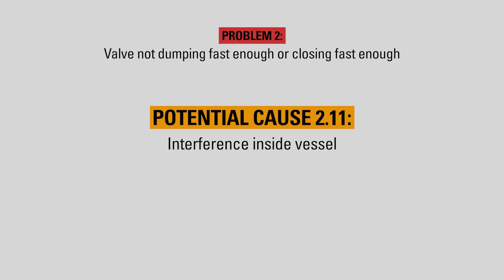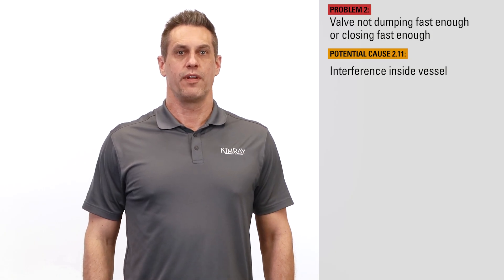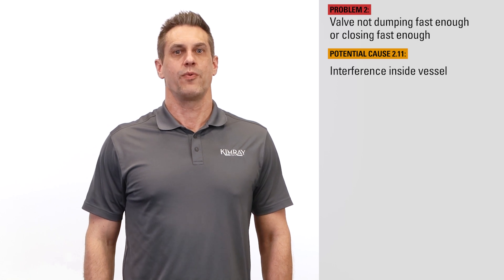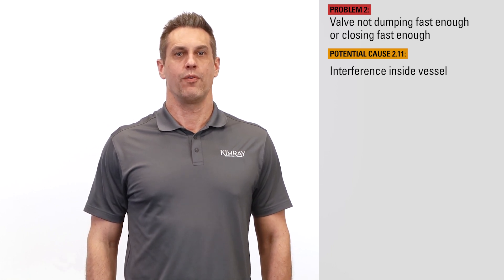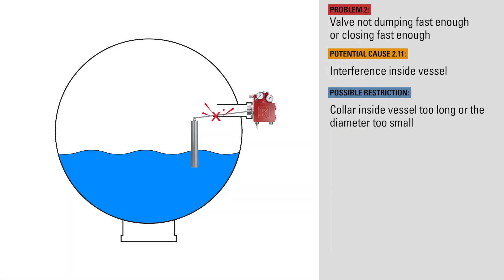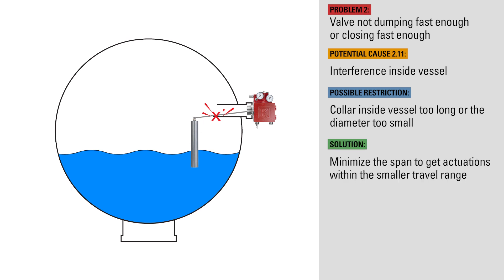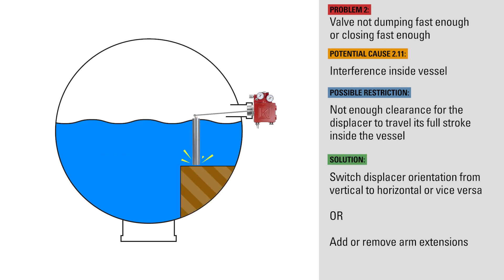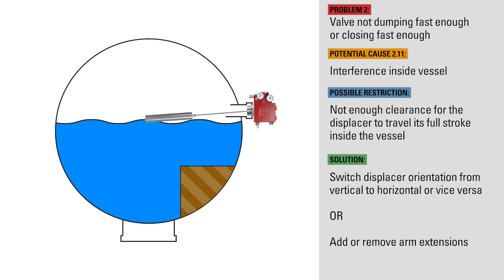If there's an obstruction inside the vessel not allowing full range of motion of the arm or displacer, this can restrict the actuation of the controller, not allowing full output or full vent flow. One possible restriction could be the collar inside the vessel being too long or the diameter too small. If this is the case, you can try minimizing the span to get actuations within a smaller range of travel. Make sure there's clearance for the displacer to travel its full stroke inside the vessel. If there isn't, you can try switching the displacer orientation from vertical to horizontal or vice versa, or adding or removing arm extensions to avoid the obstructions.